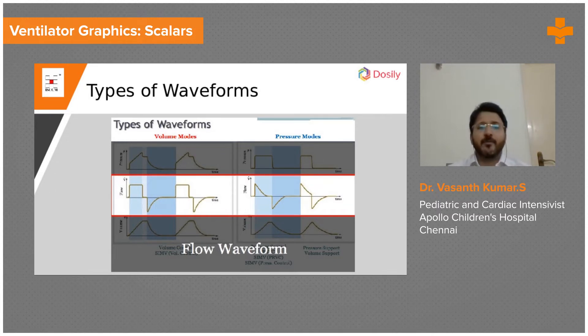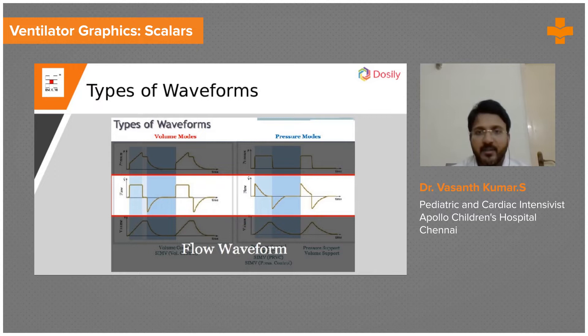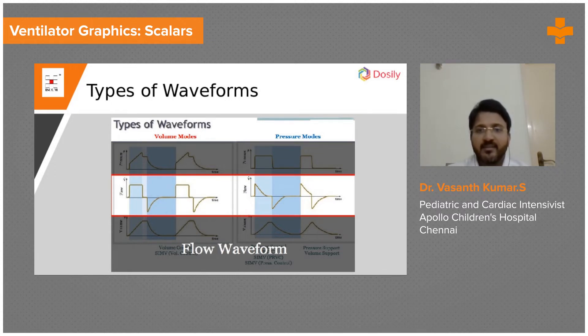Next we come to the modes. In pressure control mode, you set the pressure and you expect the tidal volume to be seen on the ventilator — pressure is the constant variable. In the pressure-time scalar, you have already set the pressure, for example 10. The ventilator will give a pressure of 10 and maintain that same pressure throughout inspiration, then go into expiration. You will see rectangular or square waveforms — this is called a constant waveform in pressure control mode.